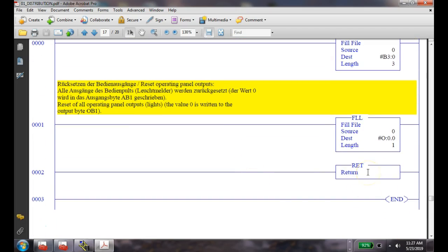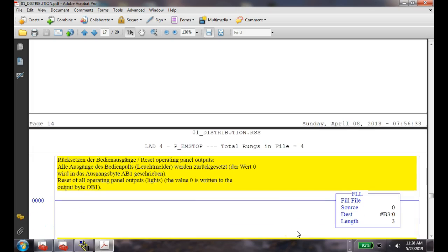But look at the last instruction in the subroutine. It's called what? Return. What would that cause it to do? Well, it's going to go back to the next rung after that JSR. So automatically it's going to go back into your main program. That makes sense? So if I was having problems with the reset or the interrupts or anything like that, then instead of me trying to find it, I would just go directly into this and see if I could figure out what's going on.